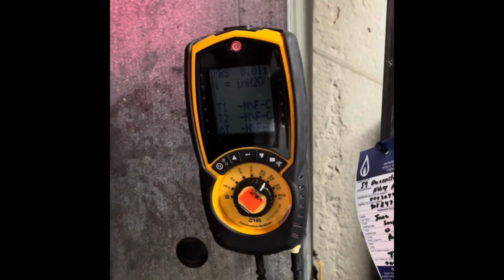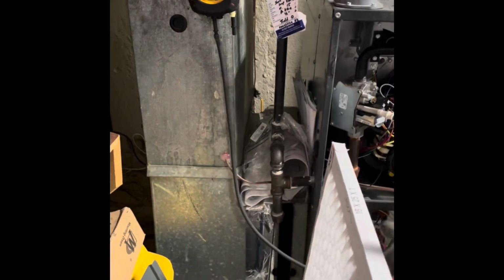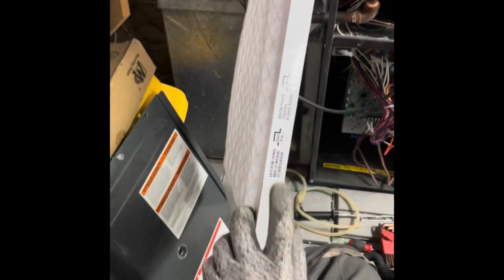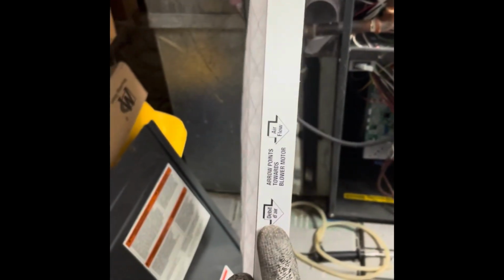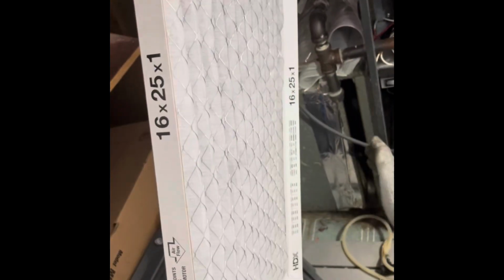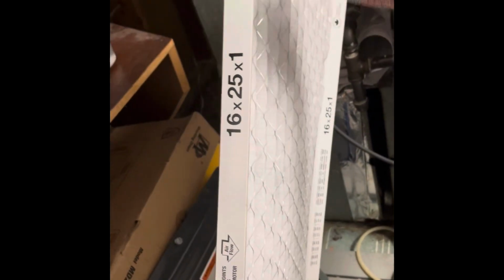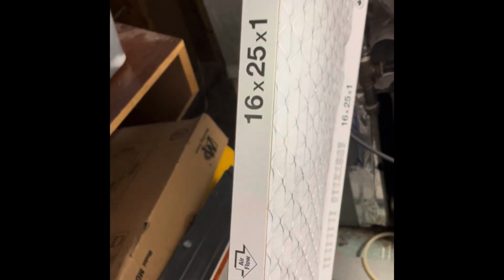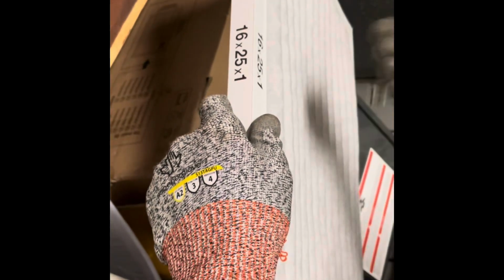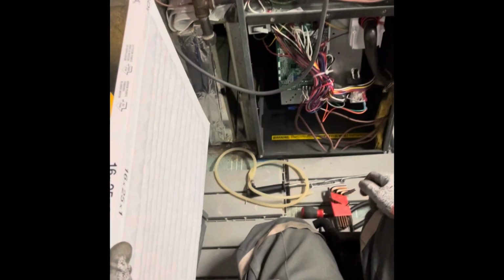And filters. So these are important. I'm going to give you guys a quick rundown on filters. So in this case, the filter is put in the right way. If we look, there are always arrows on the trim. The arrows have got to point to the furnace. We've got chicken wire, extra reinforcement on this side, so it doesn't get pulled into the blower motor in case the glue unsticks from that filter material. I've seen many times where the filter's in backwards. No chicken wire here. That material gets sucked in. Within 3 seconds, it'll take out the control board and the blower motor in one shot.